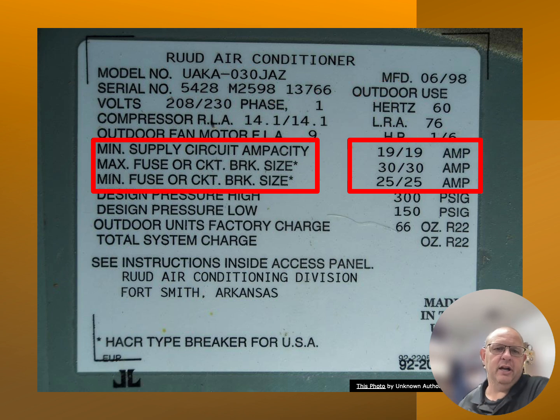Now, what's going on here with this system? I have a minimum supply amperage going to this unit. I got a minimum circuit breaker that goes on this unit. And I also have a maximum circuit breaker that goes into this unit. The type of breaker that I want to use for this is an HACR type breaker. So if I was to put the minimum size breaker in for this particular unit, what size wire would I need to run according to the NEC?